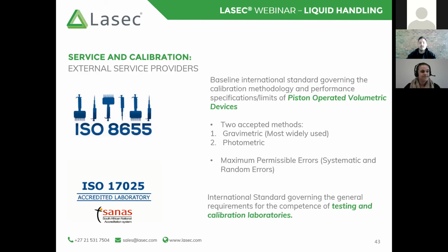All right. So these are generally carried out by accredited laboratories, either accredited by the manufacturer of the pipette that you are using, perhaps they have received training at the manufacturer, or accredited to SANAS to test or calibrate your equipment. So this would be an external service, and generally speaking with pipettes, or according to the ISO 8655 method, and depending on the importance of the work that you are doing, it is recommended that a pipette be calibrated annually.